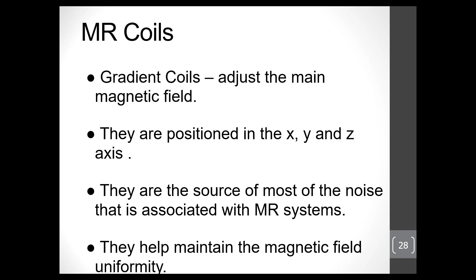And then these little fingerprint things you see on the side here, these little silver things, these are your gradient coils. I didn't know that. I knew they were in the magnet, but this is basically the sleeve over the main core. You can see the big magnet cores here, and these little gradients then kind of goose the magnetic field, the great big one, into a focused part of the scan.